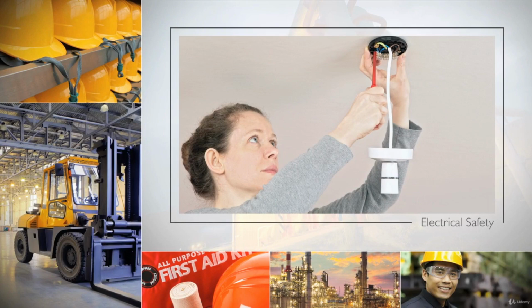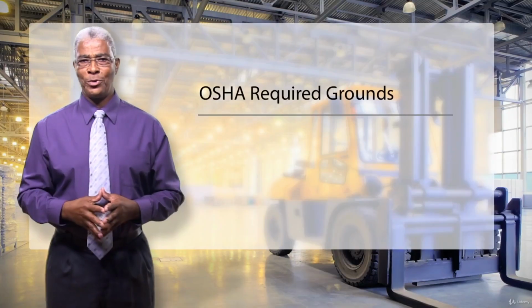If these parts are properly grounded, they will be at 0 volts relative to the ground. This means that if your body completes the circuit between the metal parts and the ground, there will be no risk for shock. Remember, without voltage, there is no electrical force to push the current. OSHA requires 2 kinds of grounds.